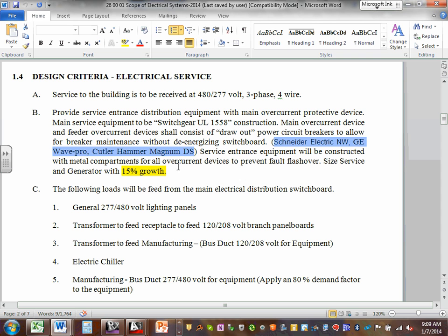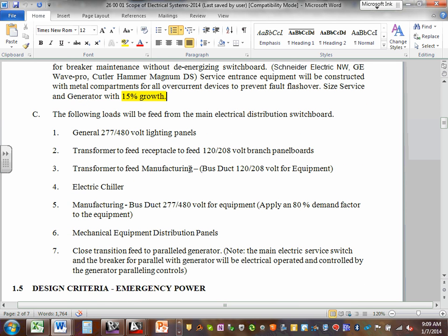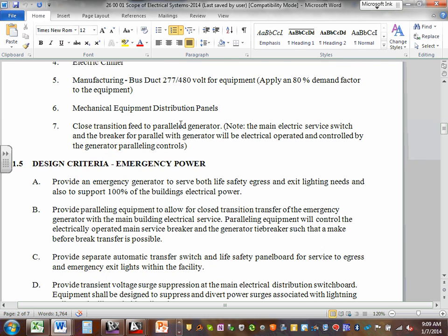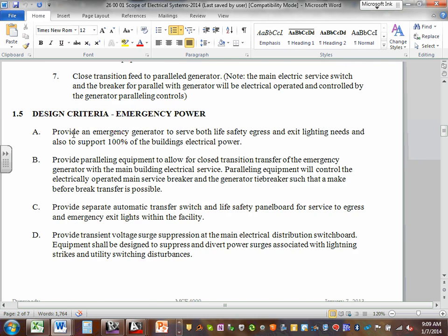Service size and generator are going to have 15% growth included into them. For the emergency power, the generator is going to be supporting 100% of the building, so you don't have to worry about sizing a smaller generator for just life safety. It's going to be the whole building, which is sometimes typical. It's definitely typical in data centers and these types of facilities that the whole building is important. Like an office space, maybe a little less. You save some money by sizing the generator smaller and just doing life safety ones.